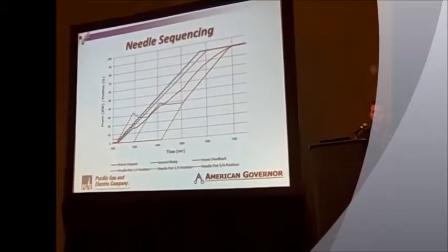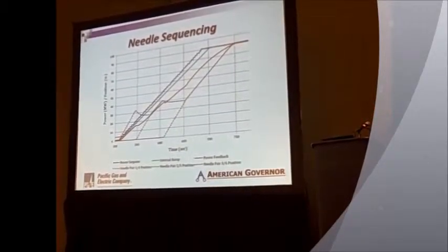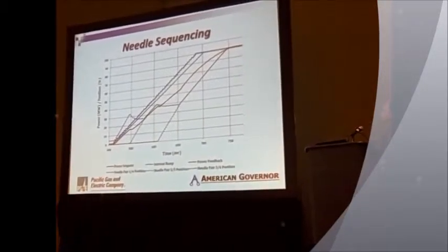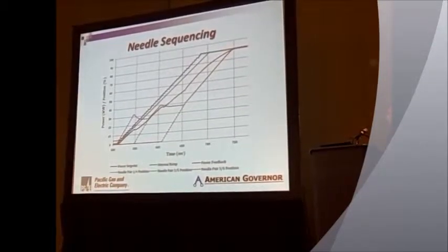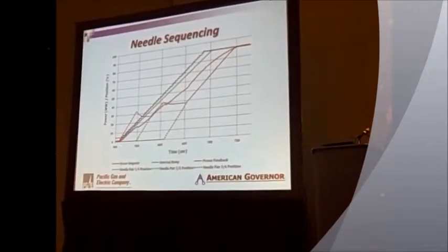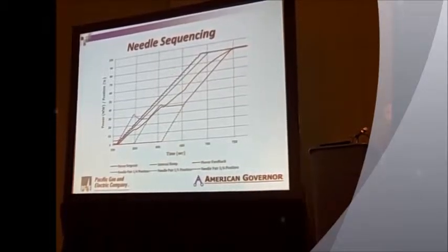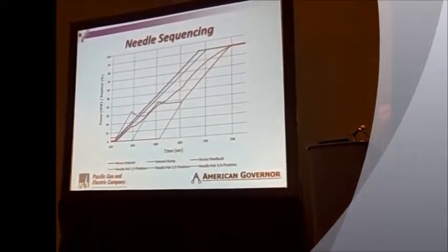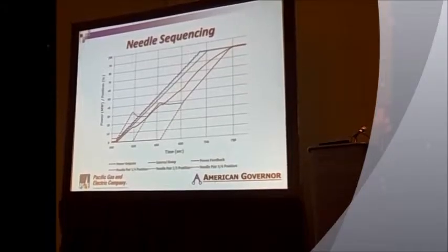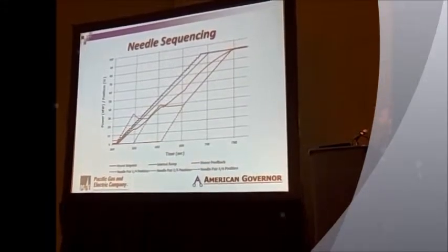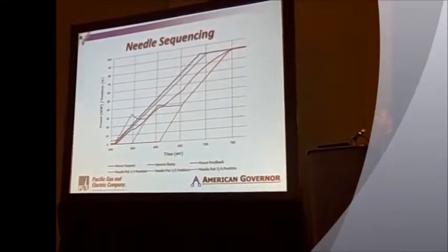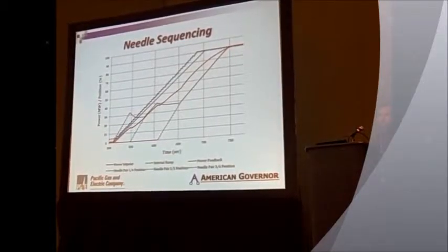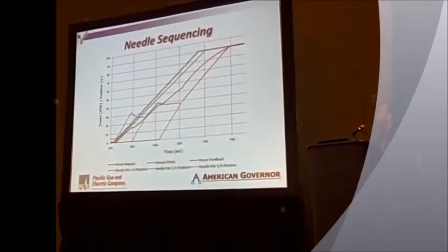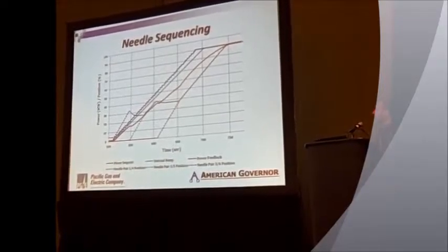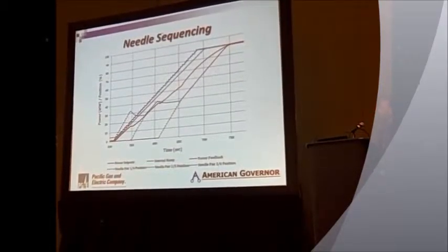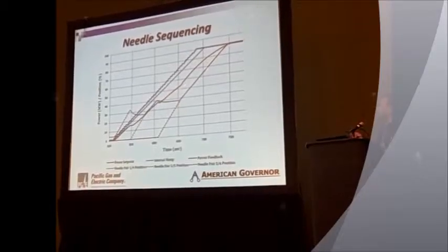So, how do we get smooth and consistent megawatt output? What we're looking at here is actual test data from commissioning, manually ramping up the megawatt set point from no load to full load with needle sequencing active. The blue line is the operator set point being ramped up in steps. The green line is an internal set point used to ensure consistent loading. And the red solid line is the actual megawatts. What I want you to notice is the more or less general smoothness and linearity of that ramp rate.